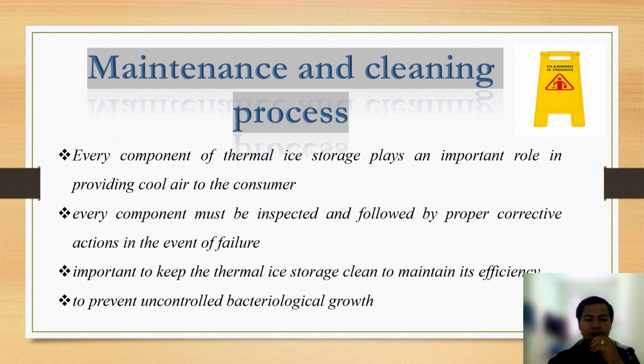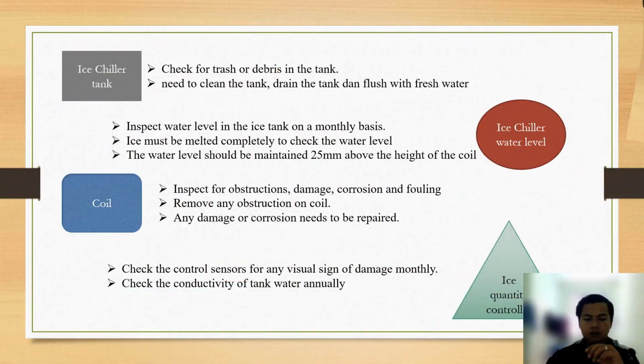Maintenance and cleaning process. The first one is every component of thermal ice storage plays an important role in providing cool air to the consumer. The second one is every component must be inspected and followed by proper corrective action in the event of failure. The third one is it is important to keep the thermal ice storage clean to maintain its efficiency. And lastly is to prevent uncontrolled bacteriological growth.